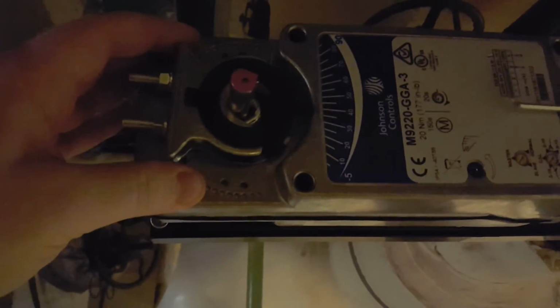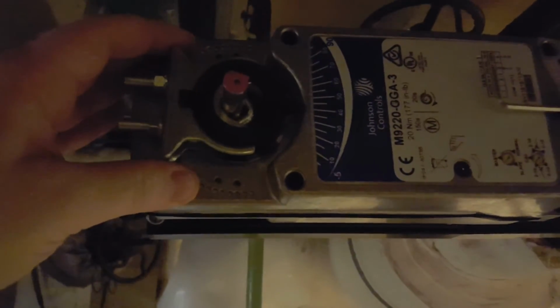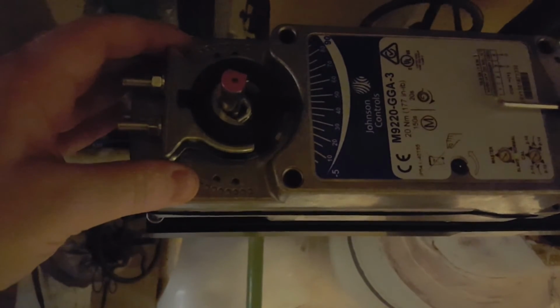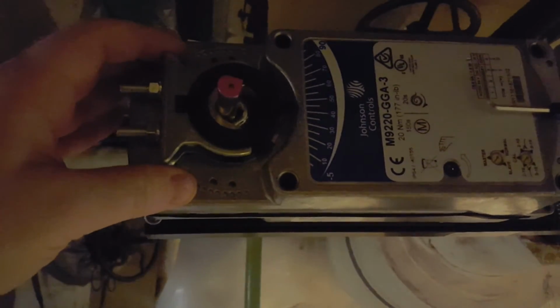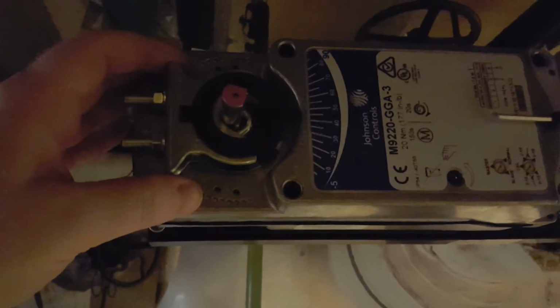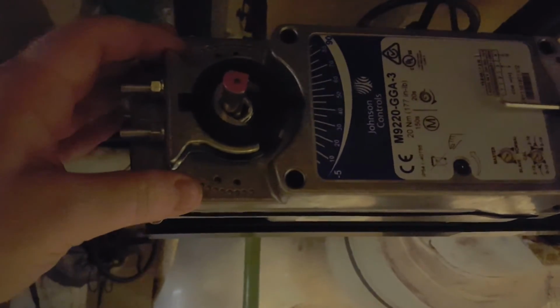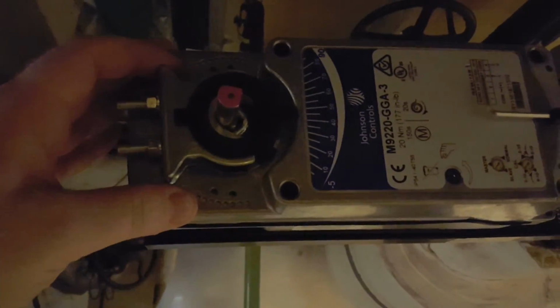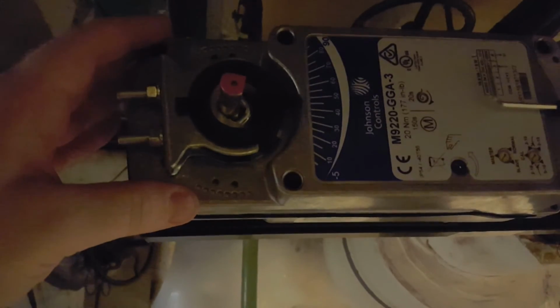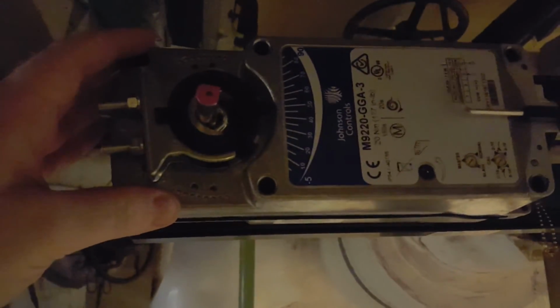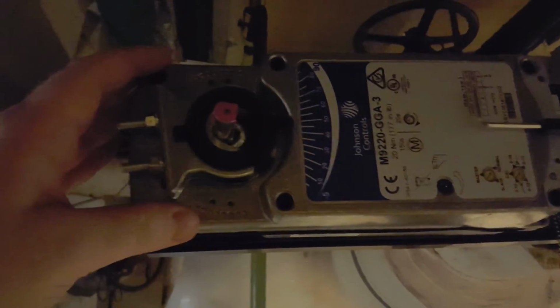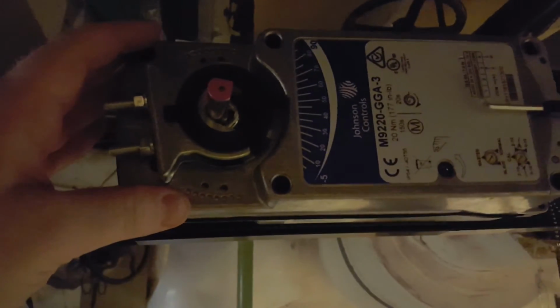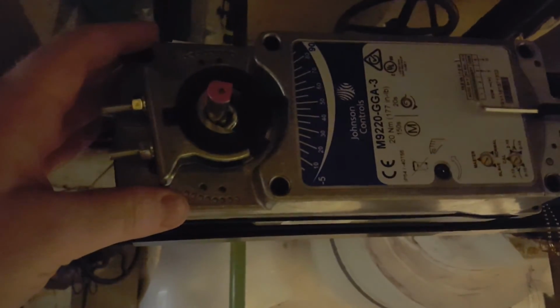Here we are stroking the valve. It's quite slow. If you have ever worked with one of these valve actuators, you know that they do not move quickly, but you can see that there is movement in this valve when we do change the output. Once again, the output is 0 to 100%. It is controlled by that PID loop. We're just testing it with an override on our system.